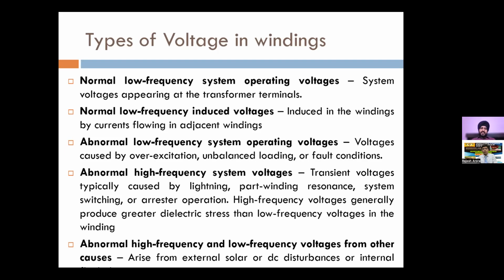And the most dangerous of them all is the abnormal high frequency system voltages. These are the transient voltages, which are typically caused by lightning or resonance or switching. So this high frequency system voltage is very dangerous because it typically occurs for microseconds to nanoseconds. So due to this very short period of time, the actual stress which is observed by the winding, which is dv by dt, is in fact very high, and it can cause sudden damage to our transformer. So these abnormal high frequency system voltages are most relevant, and mostly as per our experience also we have seen that they are something which get missed out from monitoring, and they are very relevant, and almost all utilities need to monitor them in a greater aspect.